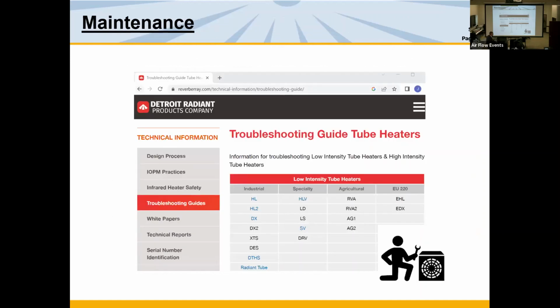Regular maintenance. The heaters can't do what they're supposed to do in the way they're supposed to do it unless they're kept clean. And I can tell you that infrared heaters are pretty doggone forgiving. We put these in some of the harshest of environments. Car washes are really tough. Agricultural swine barns are really hard. Swimming pool environments. And the nice thing with any of the heaters that we make, the tube or the unit heaters, is we can bring fresh air from the outside in. So having the ability to duct in fresh air will dramatically reduce the maintenance that's needed.